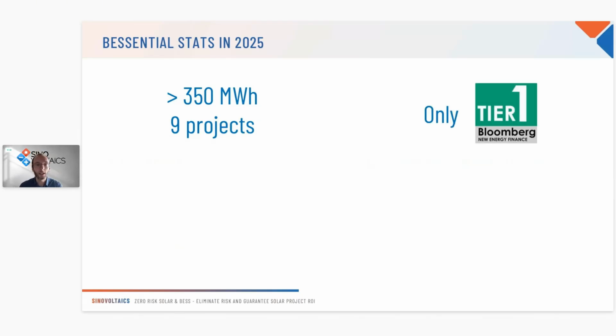We have only applied this to so-called tier 1 Bloomberg BESS manufacturers, and we found issues in two-thirds of the projects. So it's a stark reminder that while I think the Bloomberg tier 1 rankings for both PV and BESS are quite interesting, they really don't mean you should trust them blindly. If you are not careful about the quality control being performed, you may have really unpleasant surprises. So let's look at those defects.